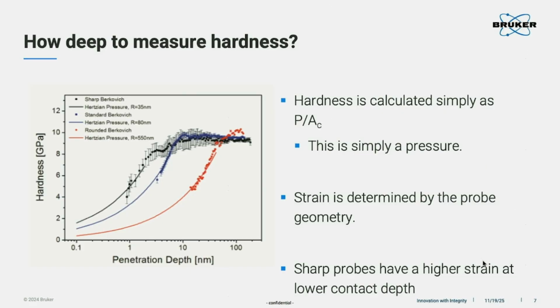For the larger tip, the stabilized zone is close to 100 nanometers. It comes later, because the tip is blunt, so you get the plastic deformation later. So selecting the probe is also very important. If you want a shallow indent, you need a sharper probe, and then you can get the hardness value at a very shallow depth, right?